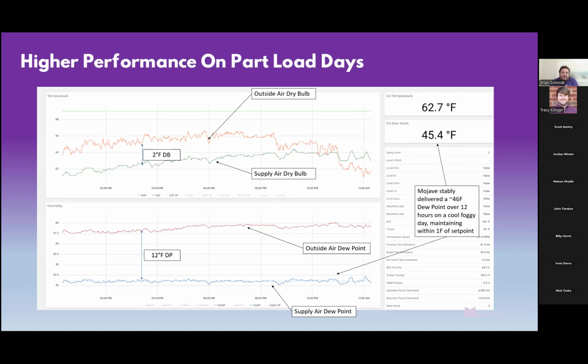But what this is showing is the outside air dry bulb and supply air dry bulb. It's really only about a 2 degree delta, so it's a part load day. Not very hot outside, but it is humid. And so the outside air dew point and the supply air dew point has about a 12 degree delta. During this condition, a traditional hot gas reheat DOAS unit would struggle to maintain the supply air dew point conditions versus the Mojave Arctic-Dry system. As you can see, that blue line all throughout the day, over about a 12-hour period, fluctuated within about plus or minus 1 degree of the dew point set point.